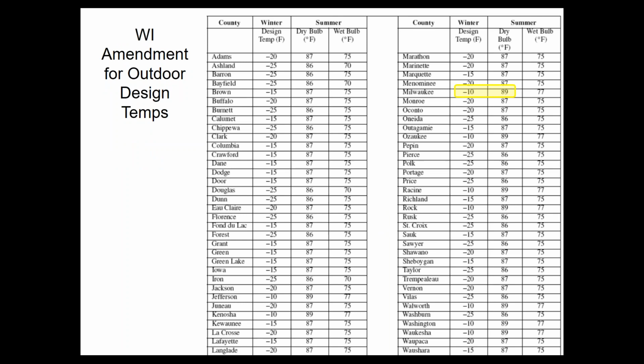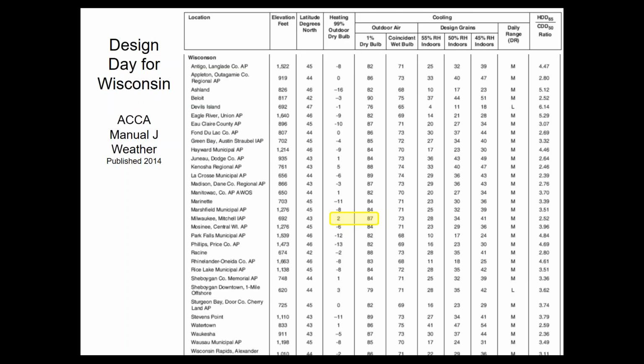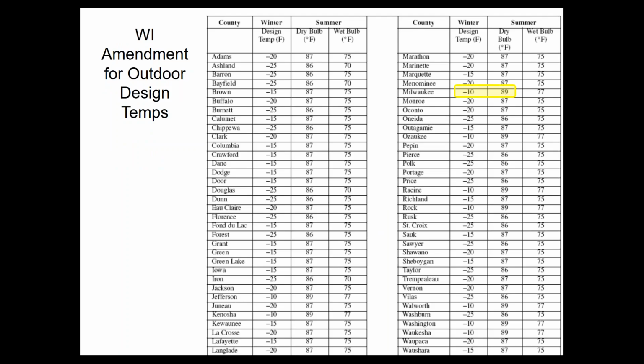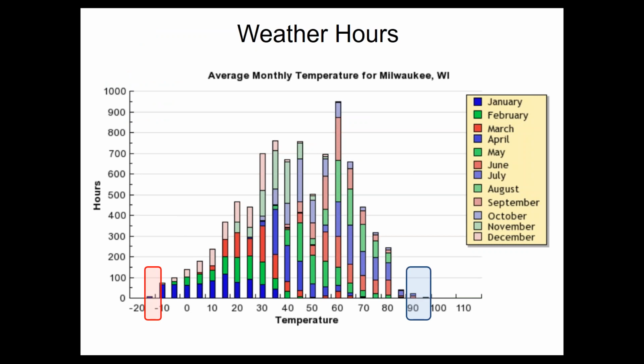That means if you were in Milwaukee, instead of 2 degrees and 87, it's instead minus 10 and 89. So that's what you have to use in Milwaukee. You do not follow the ACCA tables in Wisconsin, you follow this amendment. But once again, if I look at those temperatures outside that range, it's very, very few days, very few hours of the year even, that I'm going to have anything outside that range. So there's no reason to size for like a 95-degree day or anything crazy like that.